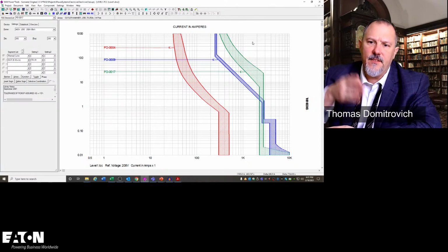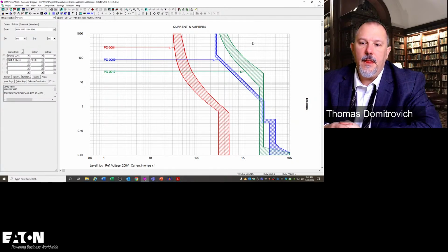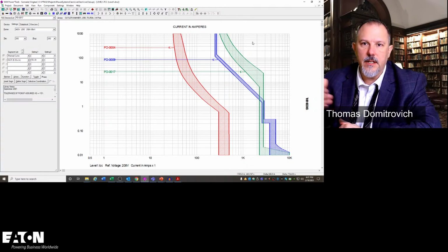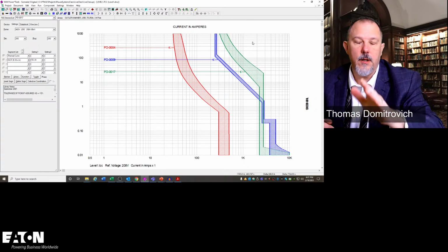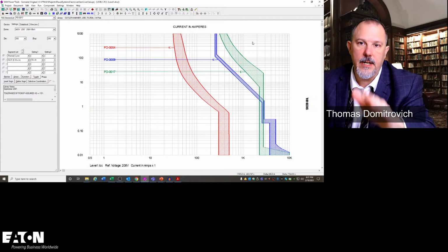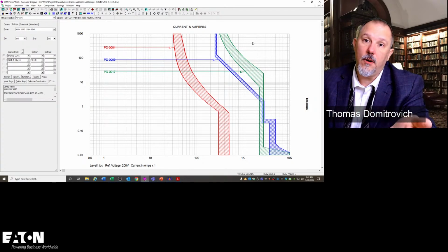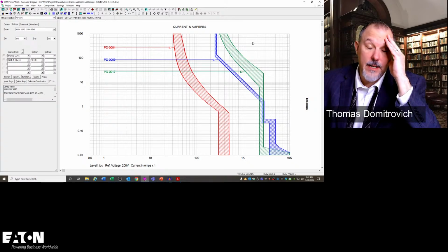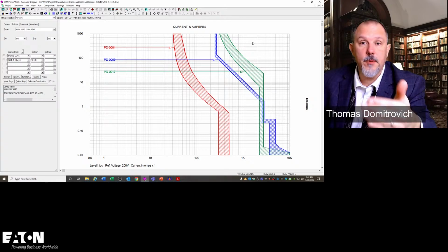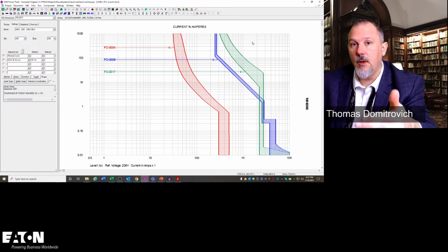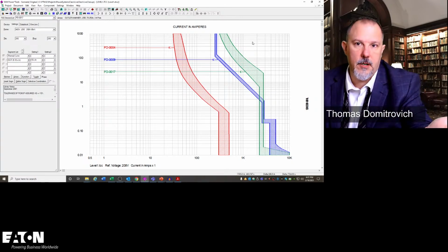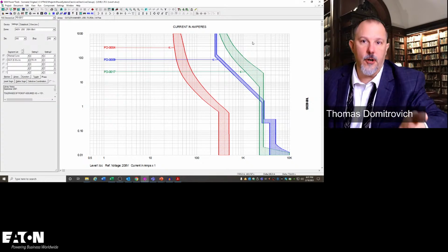I would plot my available fault current, and then I would do an analysis. If my fault current was in the instantaneous region, I would tell my customer, all right, you don't selectively coordinate to the three-phase bolted fault current. At the time when I was doing these, we didn't have 1584, so I would use the IEEE Red Book, and the Red Book would tell me what's the most common fault current in a power distribution system. It's the arcing ground fault.